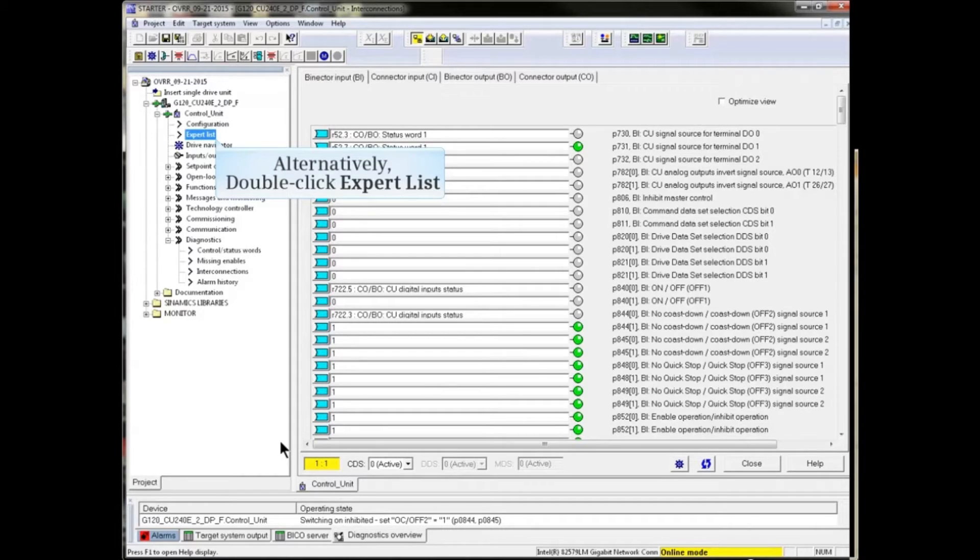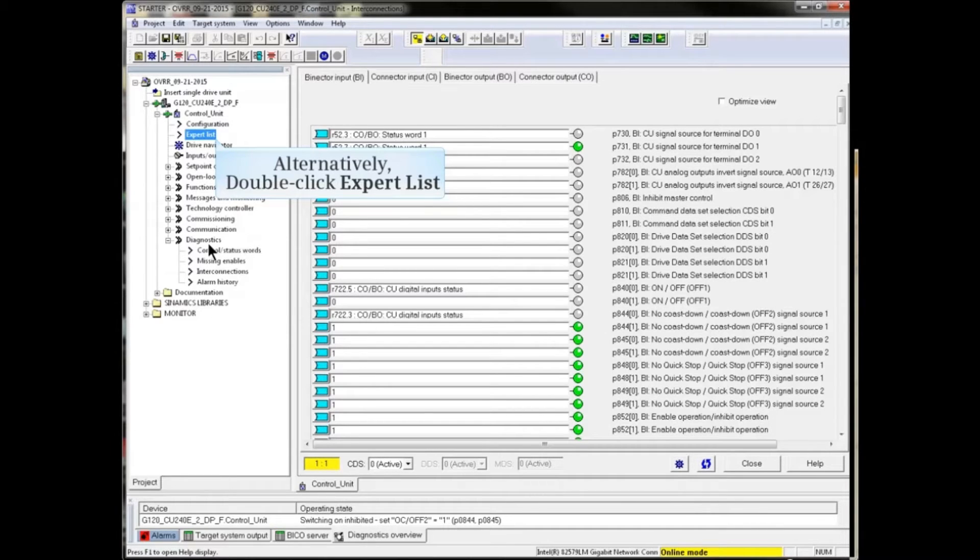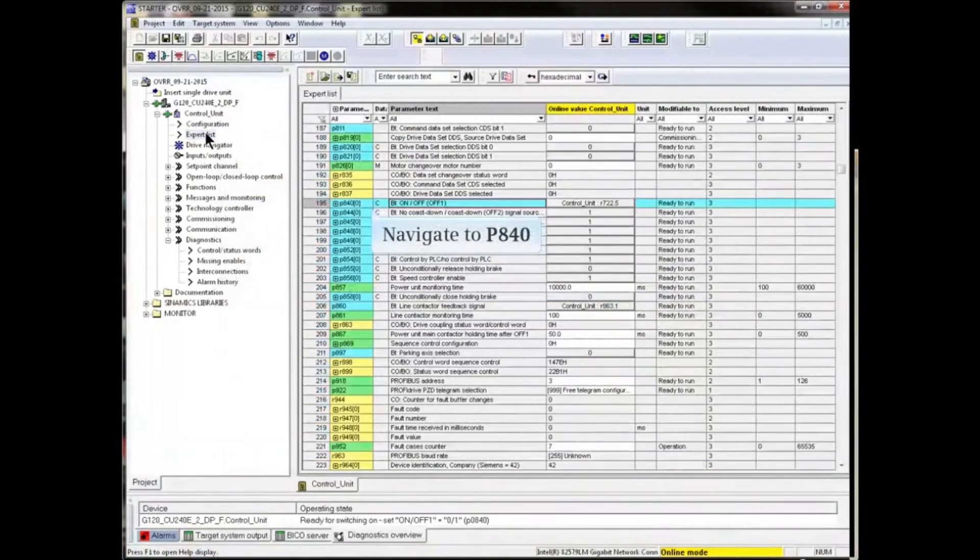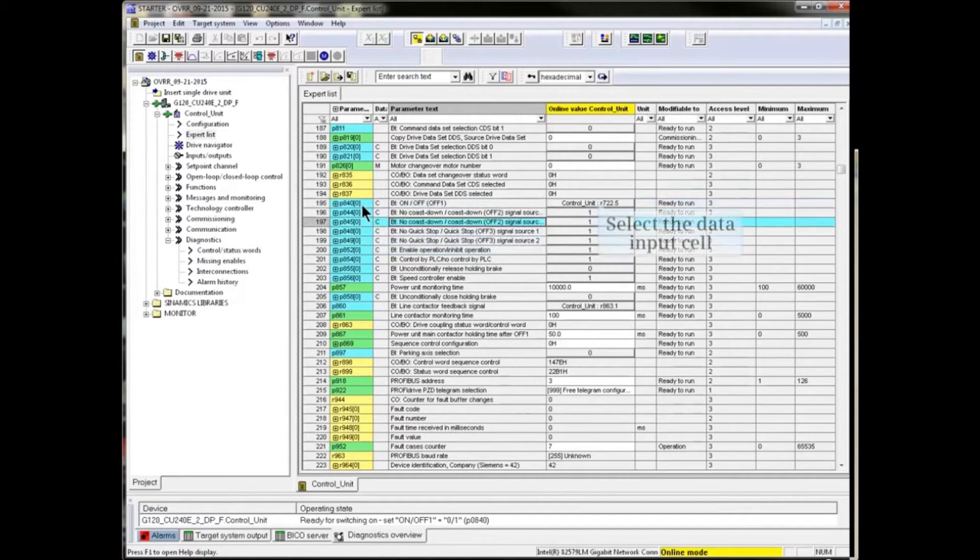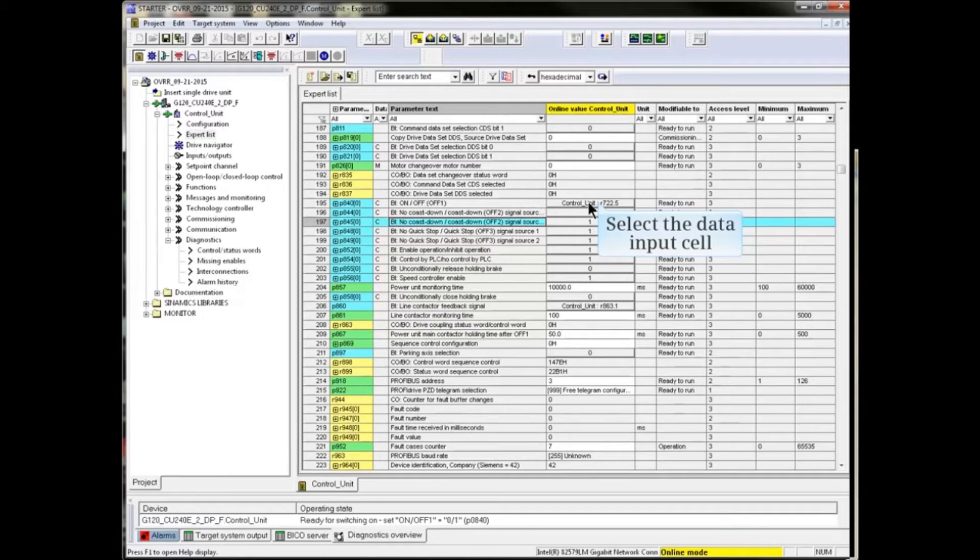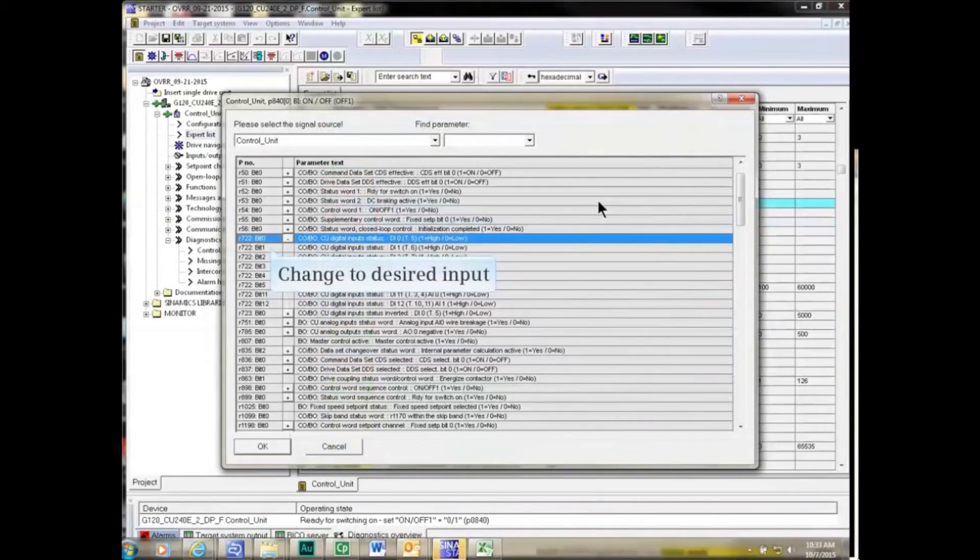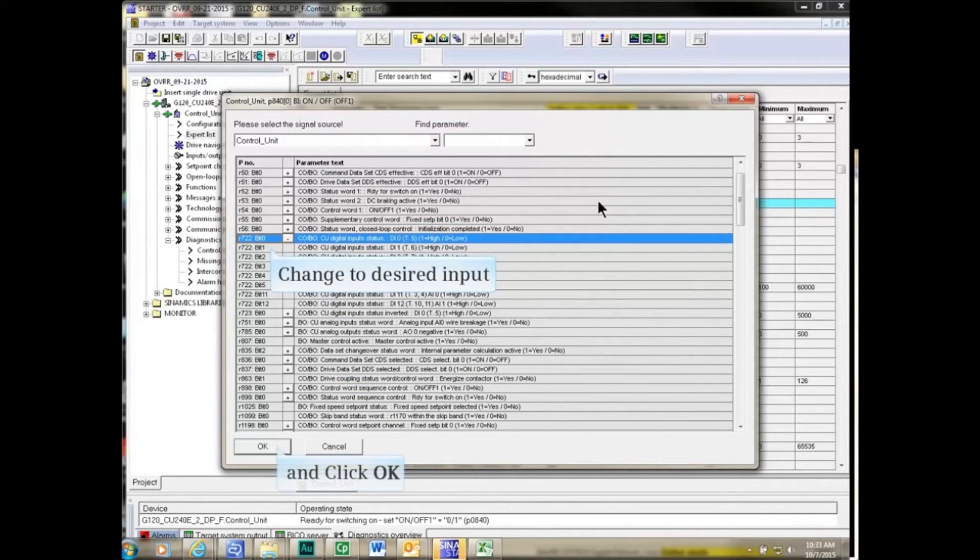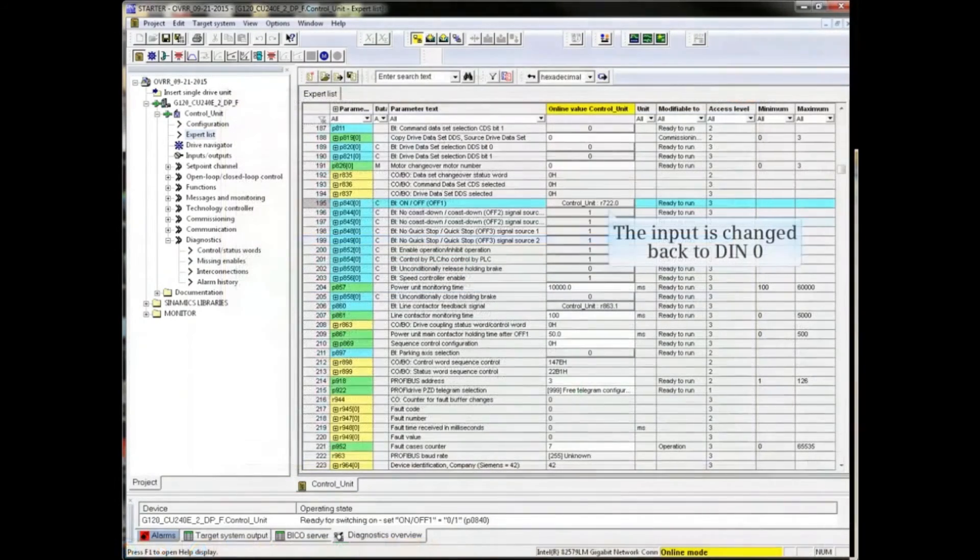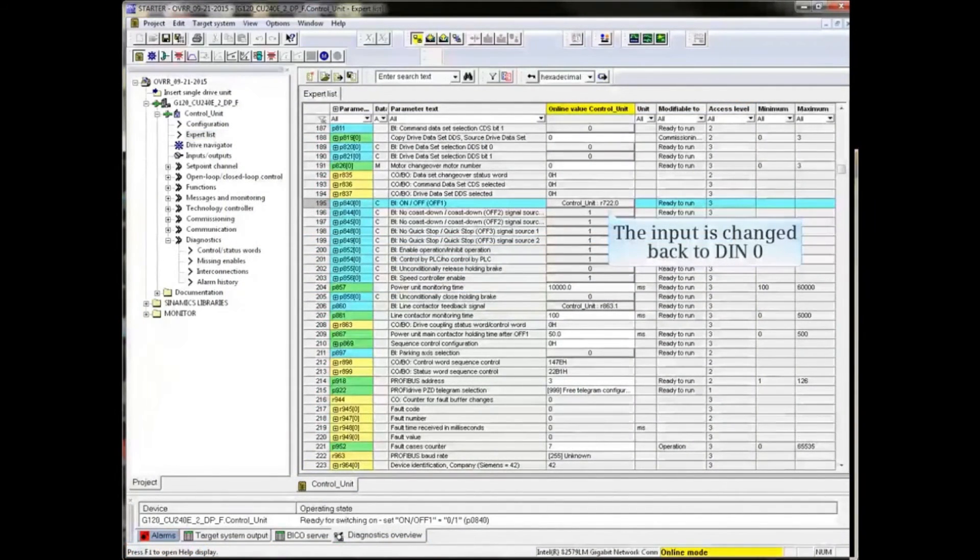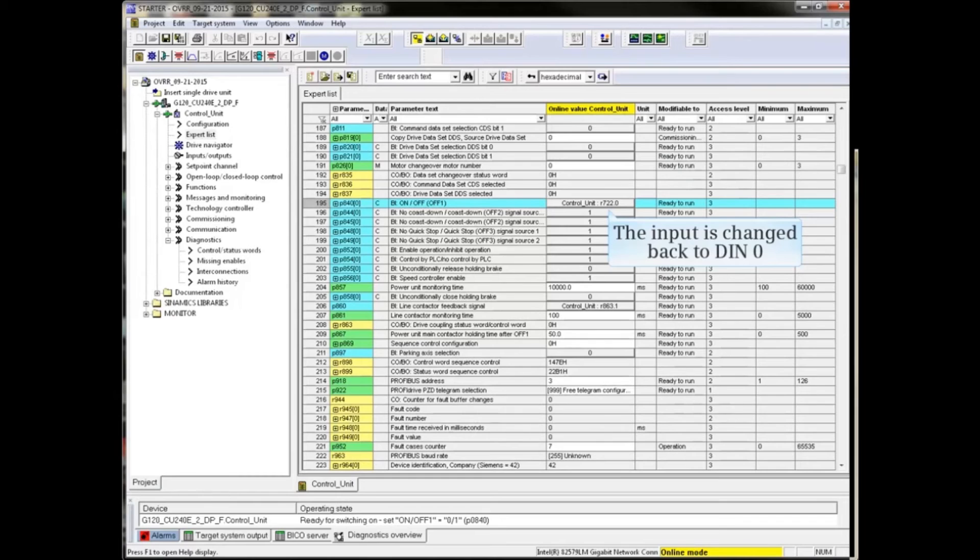Alternatively, we can make changes through the expert list. Double-click expert list from the project tree. In Expert List, navigate to P840. Select the Data Input cell and make changes as required. Click OK to confirm the change. The input has been changed back to Digital Input 0 in the example. Further changes can be made from Expert List in the same manner.